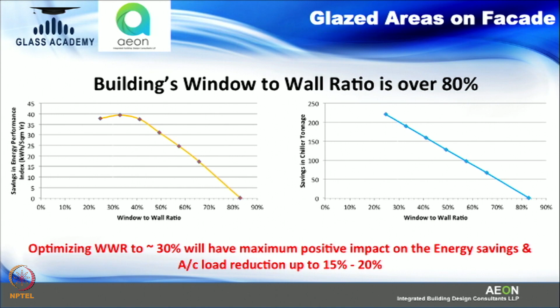In this case particularly, what we did was the analysis done for seeing really how much effect of changing the WWR happens on the energy front, energy consumption of the building, and how much impact of that comes on the AC sizing of the building. With this analysis, we found that the WWR of 30% is going to give the best effect in terms of energy savings, and also AC loads can be reduced by around 15 to 20%.